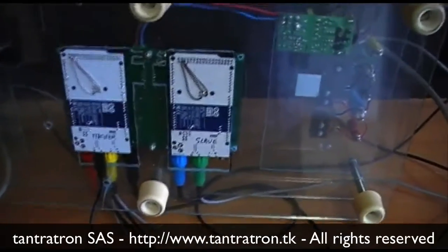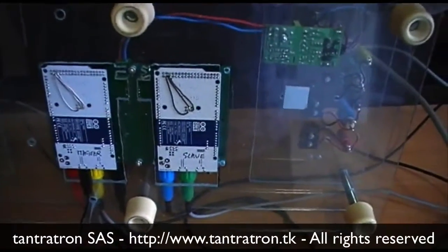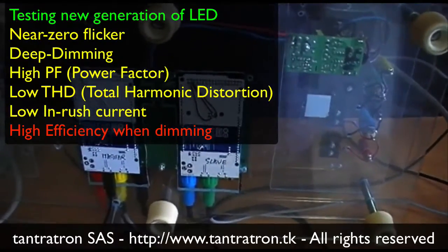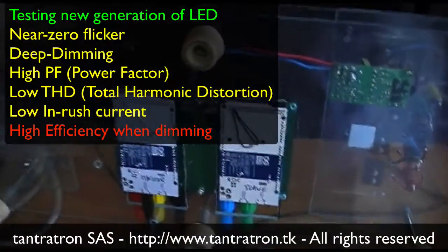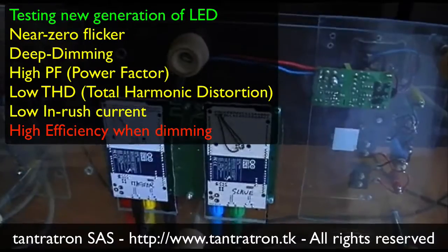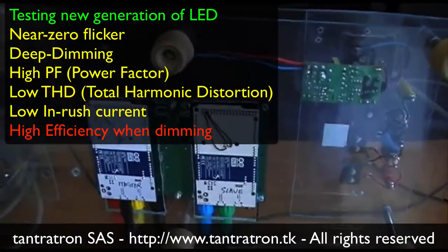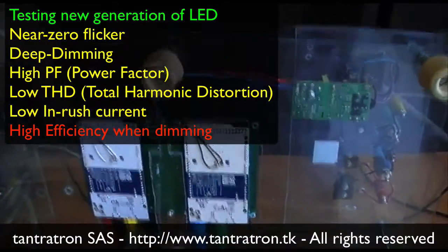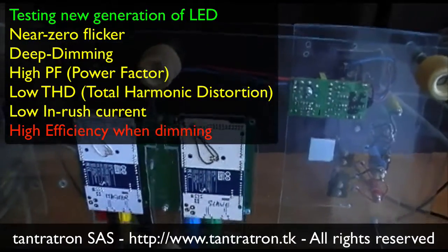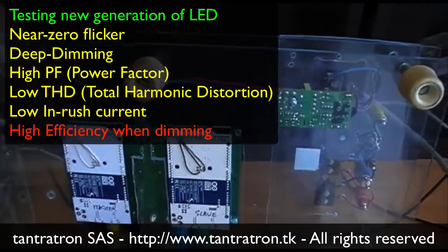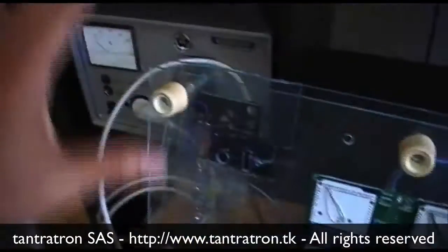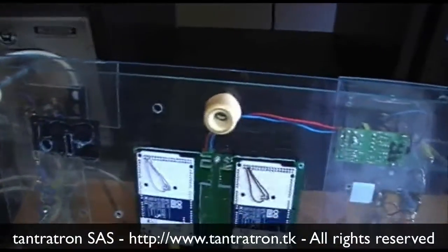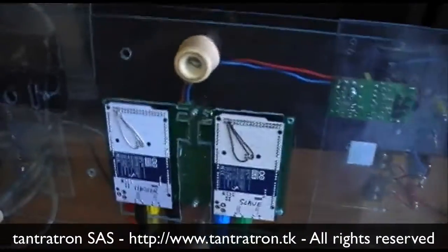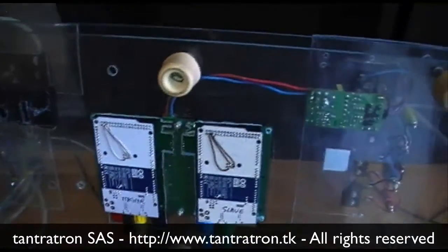So this test is ready for, let's say, the next generation of LED drivers, where we target near-zero flicker, deep dimming with high power efficiency, high power factor, low total harmonic distortion, really checking what the impact is on all these parameters when you move the grid, and the inrush.